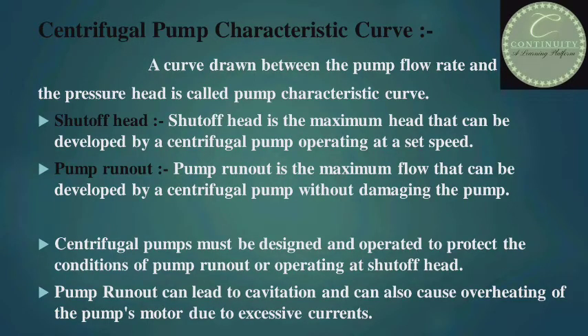Now, the centrifugal pump characteristic curve — a curve drawn between the pump flow rate and the pressure head is called the pump characteristic curve. There are two important terms: shutoff head and pump runout. Shutoff head is the maximum head that can be developed by a centrifugal pump operating at a set speed. Pump runout is the maximum flow that can be developed by a centrifugal pump without damaging the pump. Pumps must be designed and operated to avoid these conditions.